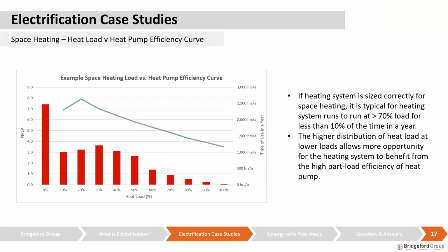No, I suppose I was just wondering what happens in the case of a heat pump for space heating that's so oversized that it's always operating right down towards the lowest point of the curve, but actually turning the system off for a time before it then needs to start compressing again. I haven't really come across this problem quite yet. But as mechanical engineers, or as good mechanical engineers, we do try to assume that the system is not oversized to the point where it's always consistently running at only 10% or 20% load. So the way to mitigate this kind of scenario would be to not oversize your system by much, and you can do that with proper energy modeling with different software available today. Yeah. Okay. Great. Thanks.